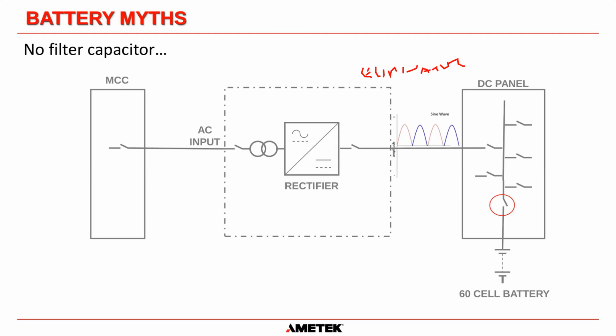Which is basically saying that you can open this breaker here and all of your load circuits will work okay, except for when somebody sends a trip or a close signal to one of these breakers. When that happens, the current required to charge that spring may be above the value of what that charger can supply. That will cause a dip in the DC voltage, which could cause issues on other load circuits. So best practice is, if you are ever going to remove your battery from service, you should tie in a temporary battery, so you're never left just relying on the charger.